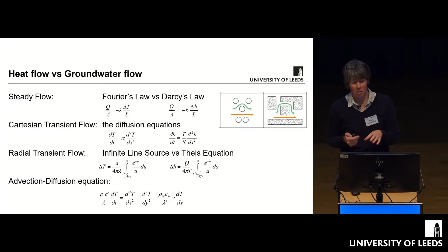There's one more equation I want to put up, for the thermal power available from the ground, which is a function of the mass flow rate at which we can extract water, either from our closed loop or open loop, the specific heat capacity of that fluid, and the temperature difference between our source and sink. This controls how much energy we can take out, if you additionally take into account the time scale you're taking it out over.